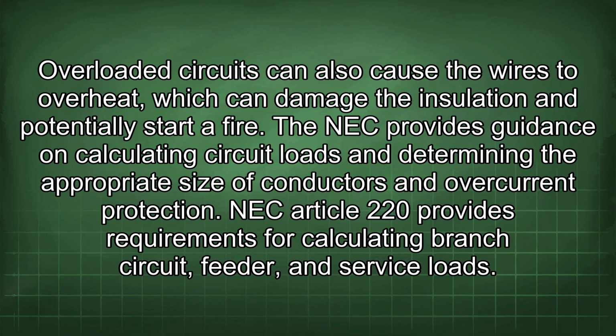Overloaded circuits can also cause the wires to overheat, which can damage the insulation and potentially start a fire. The NEC provides guidance on calculating circuit loads and determining the appropriate size of conductors and overcurrent protection. NEC Article 220 provides requirements for calculating branch circuit, feeder, and service loads.